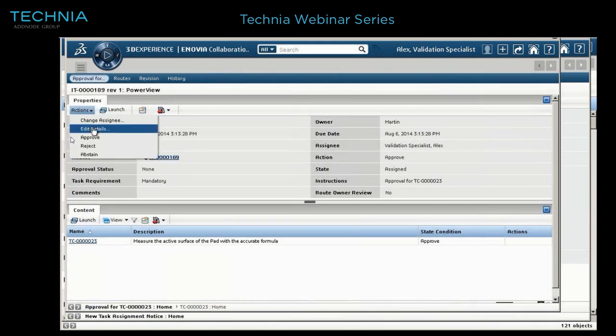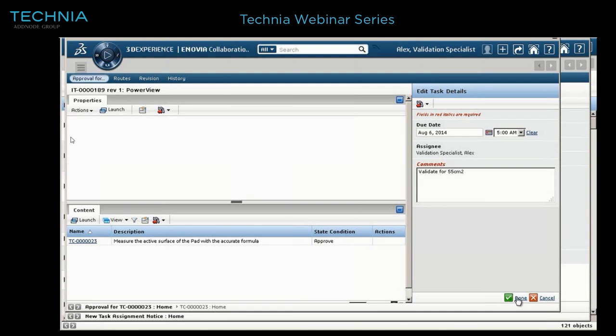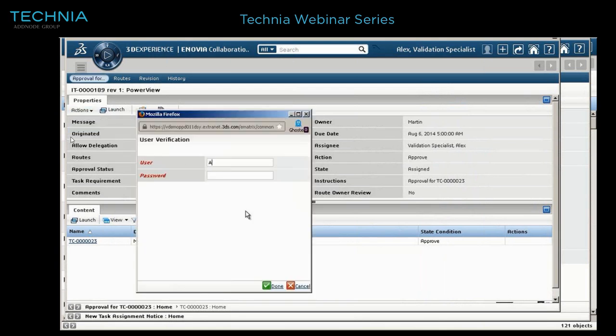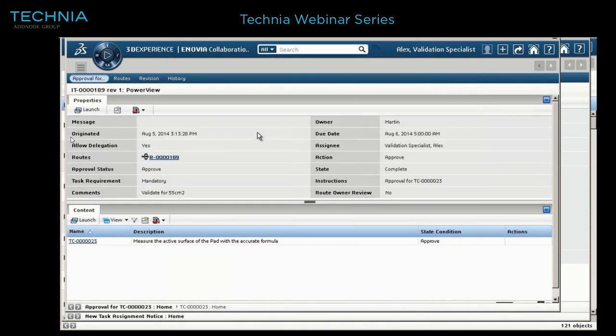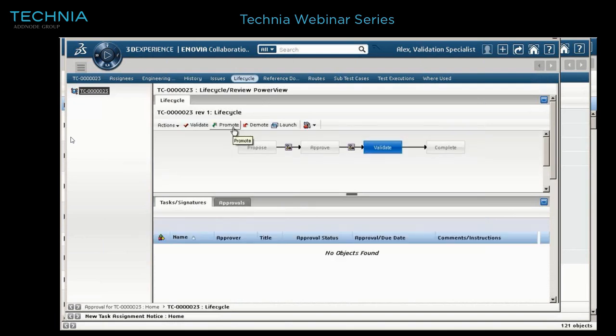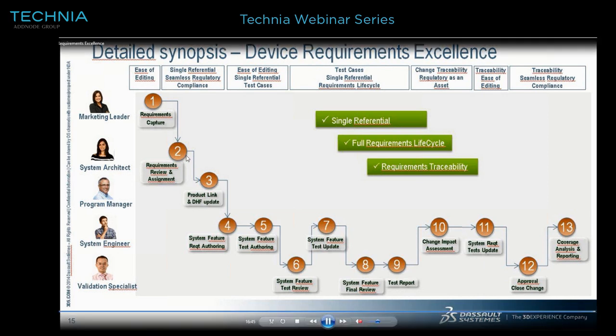Go in and perform a formal approval. So let's add a comment. It's mandatory. So just have a comment that this is what was updated and this is the new validation. I approve it. I add my signature and my blessing to this validation, and I add my trace in the audit trail. And I promote it to validated state. So that's how it might look.